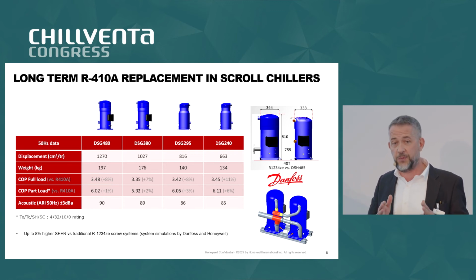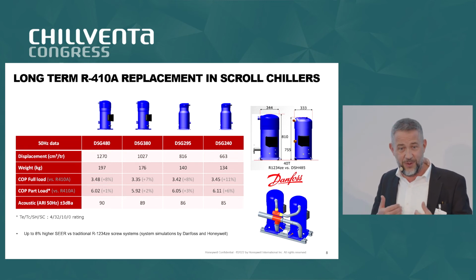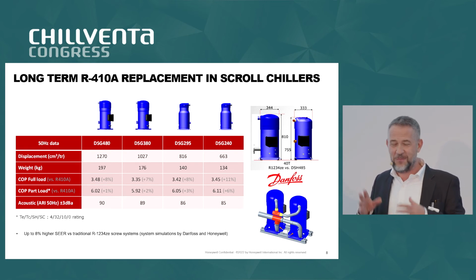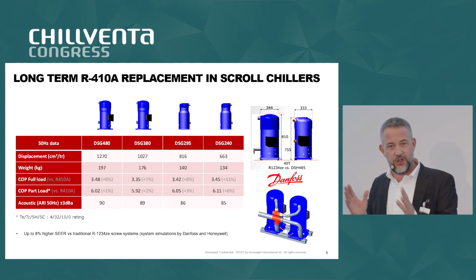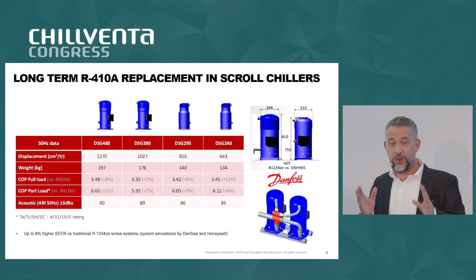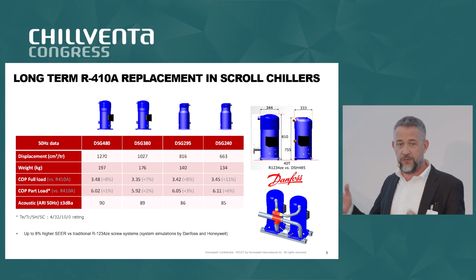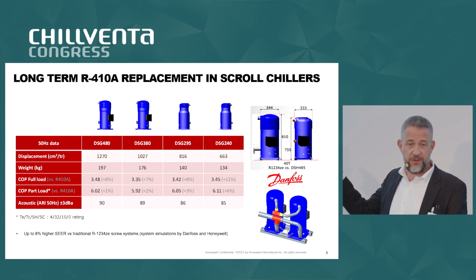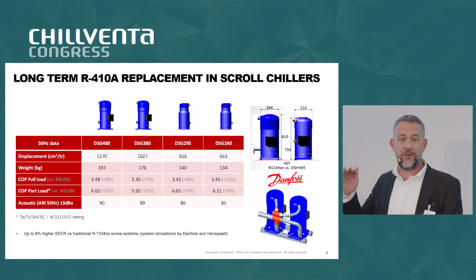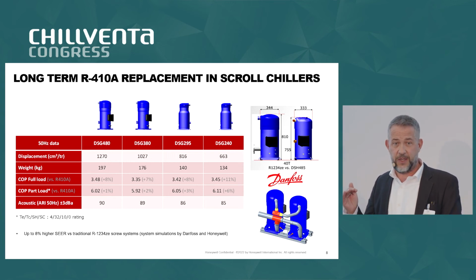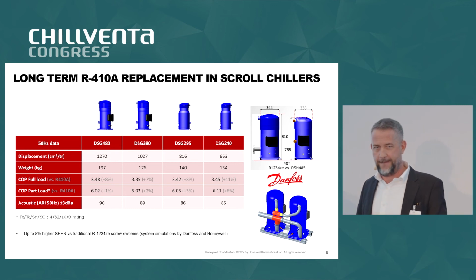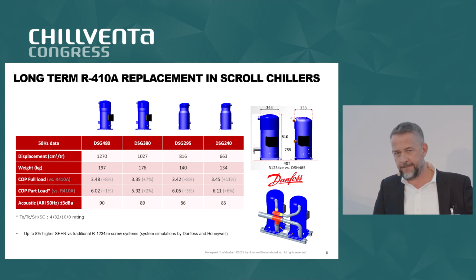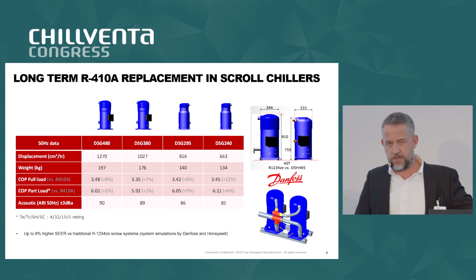I'm not saying variable speed isn't better. I personally published, when I was younger, work on variable speed versus fixed speed in chillers. There is a benefit, but the cost is really huge. The cost of a drive on this kind of compressor may be at least at the same level as the cost of the compressor itself. That's the problem. But that combination is already accepted in the air conditioning field, so talking about chillers versus air conditioning, that cost has already been adopted there.